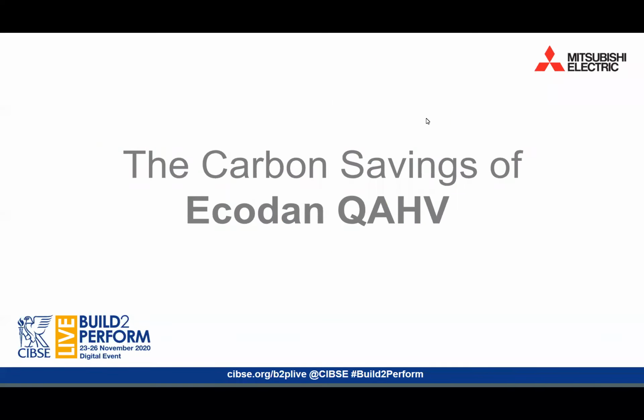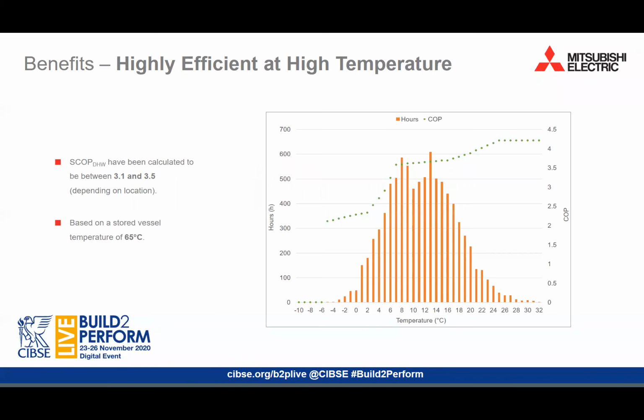So now we understand how to maximize the benefits of this technology, let's take a closer look at the potential carbon savings. The QAHV is highly efficient at high flow temperatures. In fact, depending on the location in the UK, the SCOP DHW can be as high as 3.5 when delivering a storage temperature of 65 degrees Celsius. The figure here shows the bin data for London, given the number of hours per year spent at each ambient temperature, and also the spot COP data for the QAHV providing 65 degrees Celsius into a vessel at that corresponding temperature. By calculating the annual delivered energy and dividing by the annual input energy, we calculate the SCOP DHW, which for this example is 3.43.